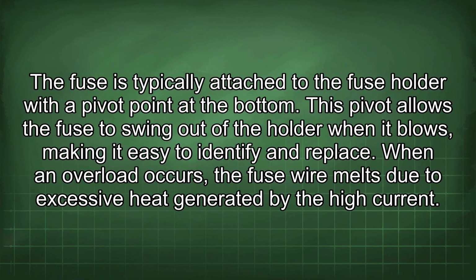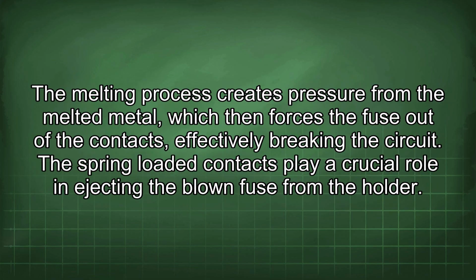conditions. The fuse is typically attached to the fuse holder with a pivot point at the bottom. This pivot allows the fuse to swing out of the holder when it blows, making it easy to identify and replace. When an overload occurs, the fuse wire melts due to excessive heat generated by the high current. The melting process creates pressure from the melted metal, which then forces the fuse out of the contacts, effectively breaking the circuit. The spring-loaded contacts play a crucial role in ejecting the blown fuse from the holder.